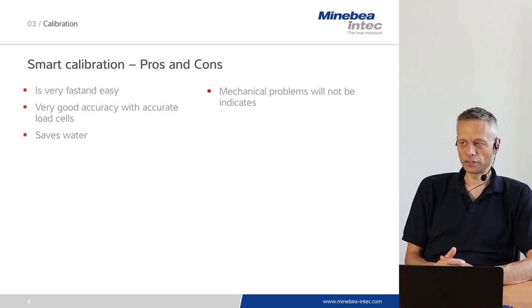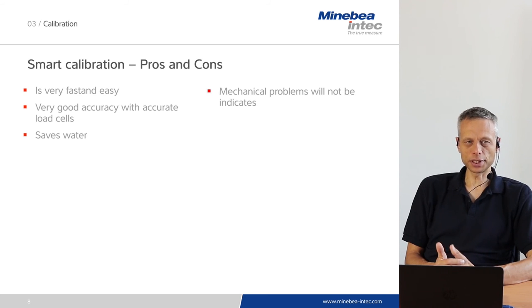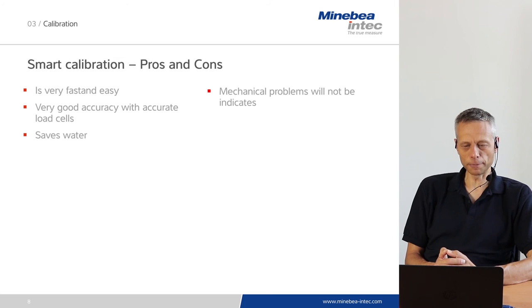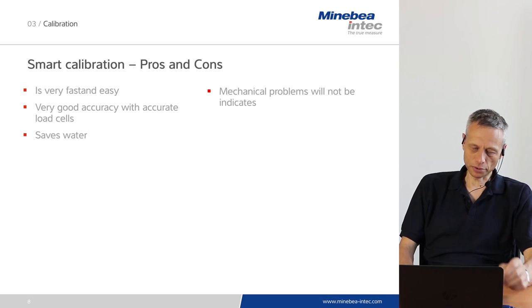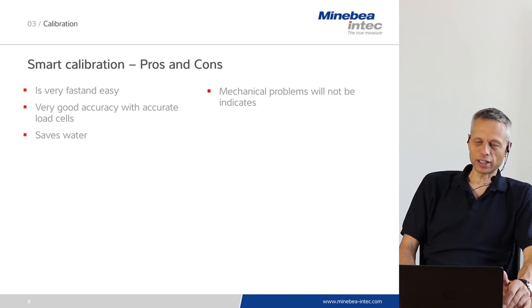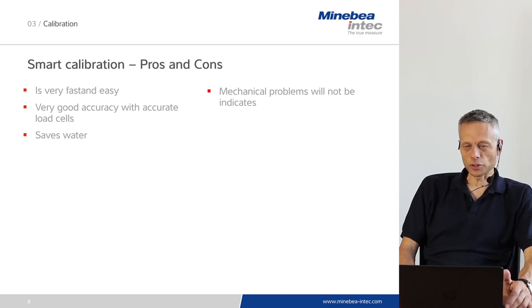Specifically, if constrainers are blocked, if load cells are not aligned properly, or if there is any hard connection of pipes to the vessel which can affect the weighing result, this will not be detected by the smart calibration method.